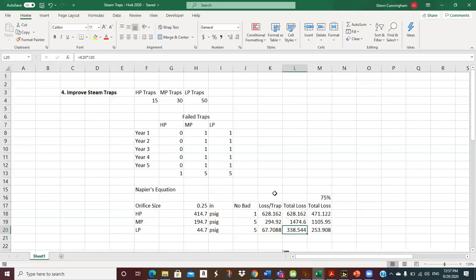So that's my orifice size. Number of bad traps. Loss per trap: 0.5143 times 0.6 times π·d²/4 times the pressure — at high pressure that's 414.7 PSIA. For individual traps: high pressure ~628, medium ~295, low ~68 pounds per hour. Multiply by number of traps — one high, five medium, five low. I said project that you can save 75% of this: so 471, 1,105, and 254 pounds per hour. Then I ran a steam demand reduction in MEASURE: 0.471, 1.106, and 0.254 thousand pounds per hour. That was my approach.